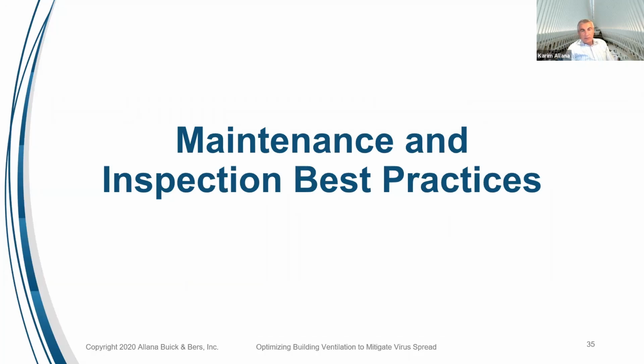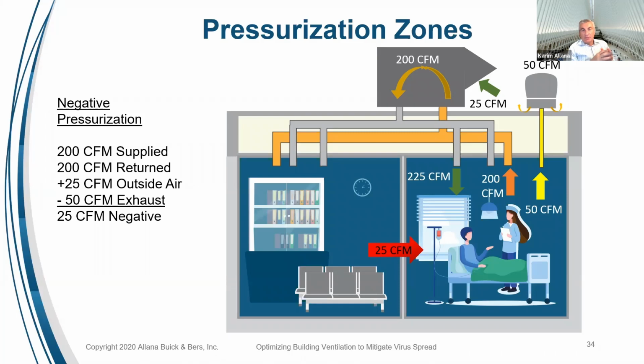The pressurization, I think, is a very critical aspect of healthcare facilities, nursing homes, where, as we all know, the largest spread in any kind of facility has been nursing homes. And part of this type of concept that the previous slide was mentioning is really important in managing the virus spread within an occupied space, especially with one HVAC system that is common to that occupied space. And so often a modification would need to be done to these systems, either adjusting and controlling the flow of air or adding additional exhaust or additional capacity or duct work to make this work. So it's not simple, but we do believe that it is necessary to lower and prevent the spread in those facilities.